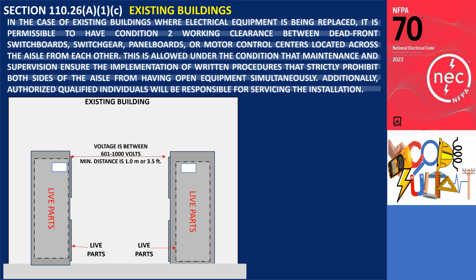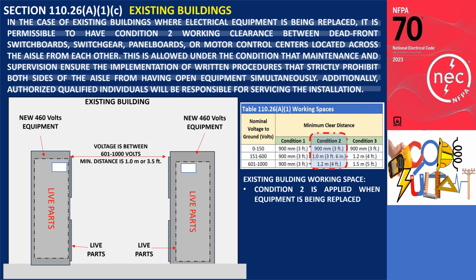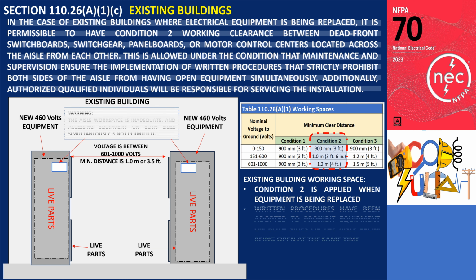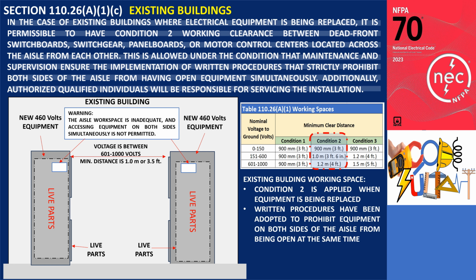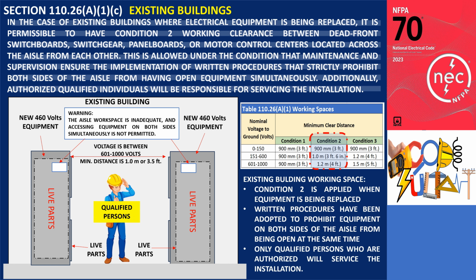This section permits some relief for existing equipment being replaced if it is not practical to increase the existing workspace, by allowing condition 2 distances instead of condition 3. However, this only applies if there is maintenance and supervision of the building to ensure that written procedures have been adopted to: 1. Prohibit equipment on both sides of the aisle from being open at the same time, and 2. Ensure that only authorized qualified persons are allowed to service the installation.